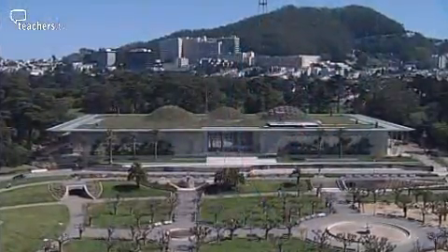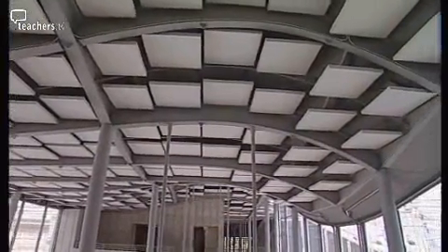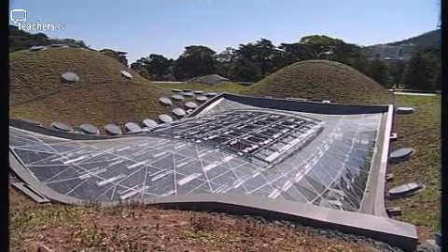As you know, there is a landscape roof that undulates. The wind blows over and under and over, and as it goes through those mounds, it sucks air up, because as you know from the interior, the hot air will rise, and the wind blowing over the top of the roof will then pull that air out naturally with no mechanical ventilation.